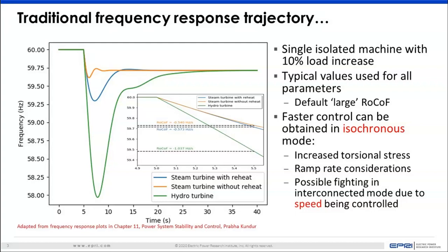And because speed is a controlled quantity, and you don't have the speed of any generator being exactly the same value at all points in time, you can have infighting with the variety of controls that you have. Now, the reason for bringing this figure back to the forefront is that it allows us to recognize that even with machines, you can have that kind of classic L shape of response, as shown by the orange curve here, but we also have machines which do have a significant lag time in responding to the events on a system.